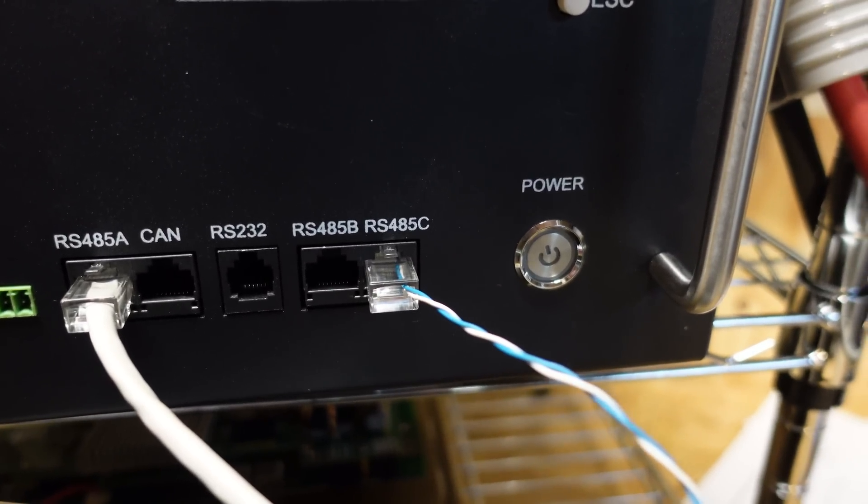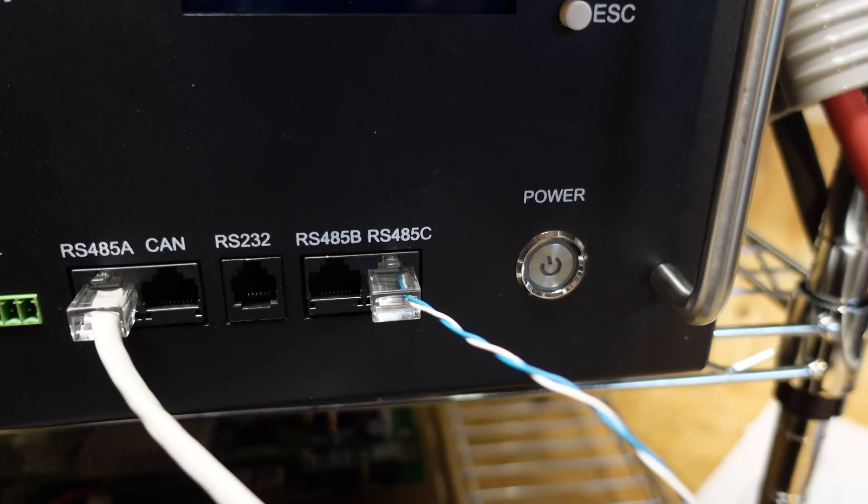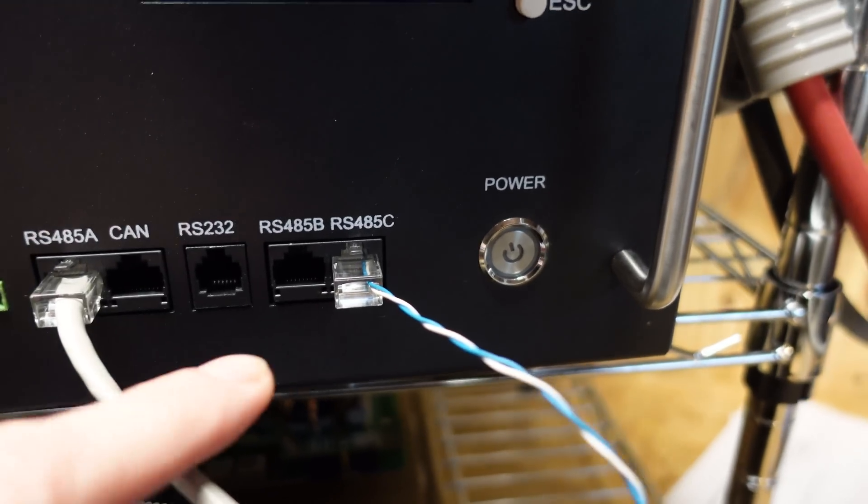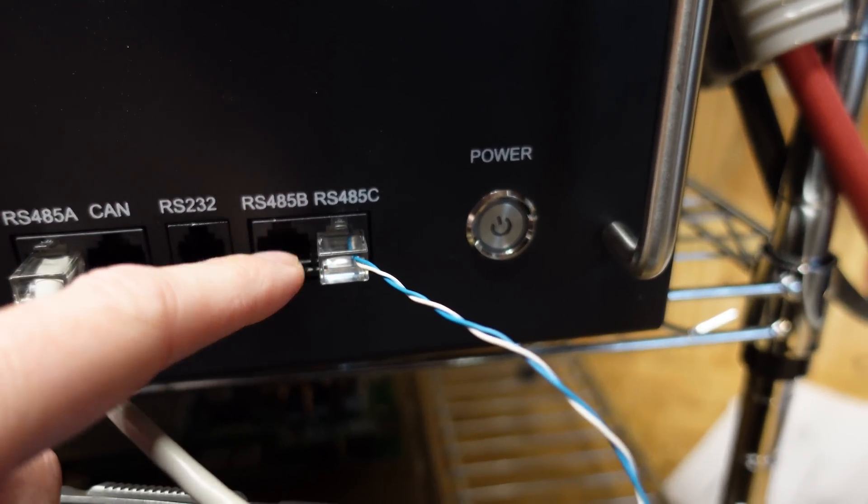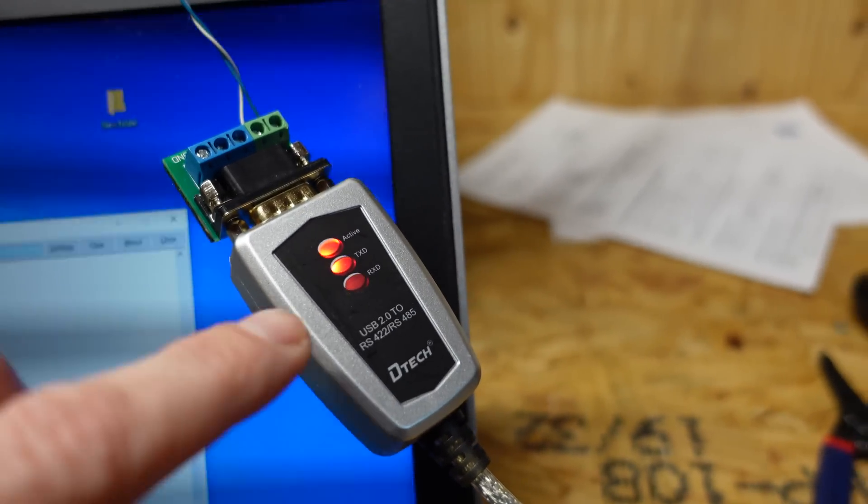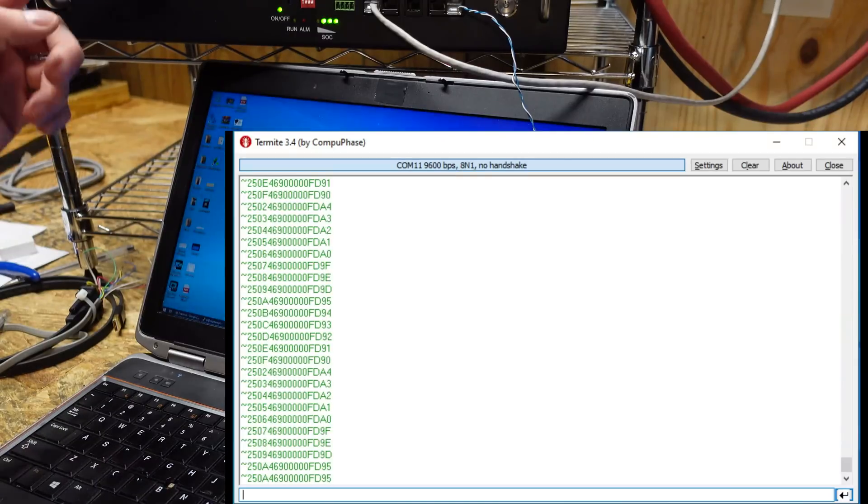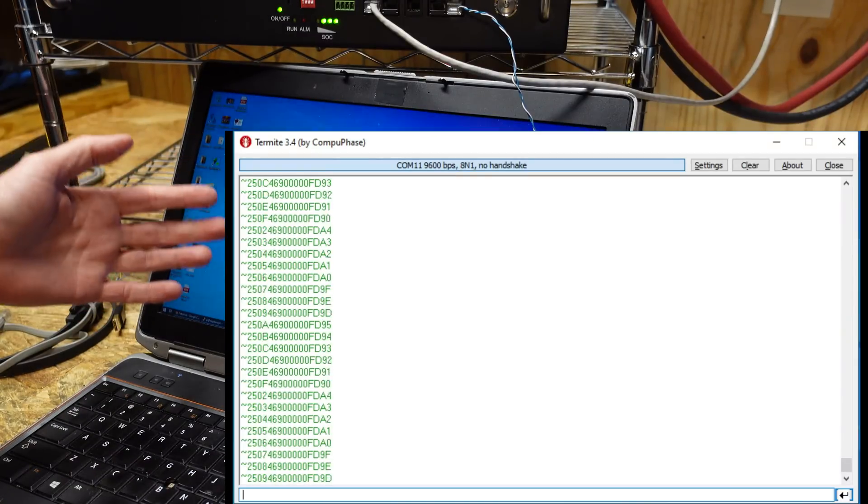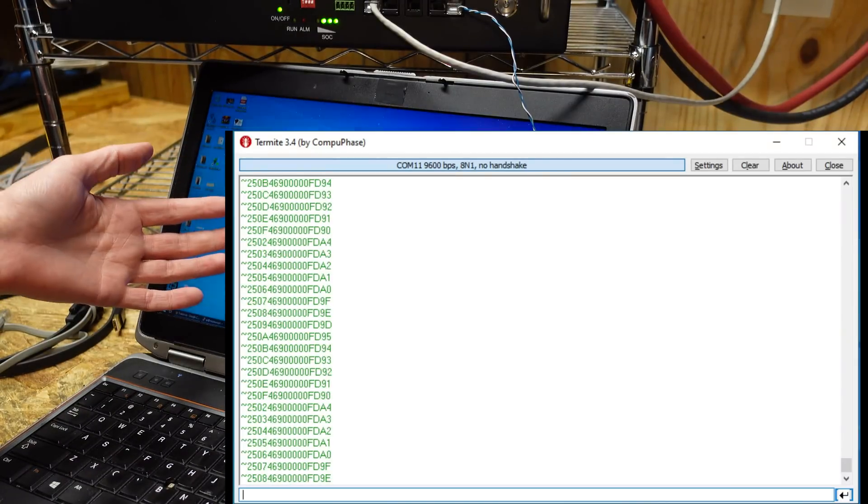All right. So, I've got it plugged into RS-485C just to demonstrate that the pinout of this cable, just to demonstrate that the pinout of the pins are correct. So, that's going down to this adapter. You can see the receive lights blinking. And on the screen here, we can see that it is clearly receiving data. So, we know the pinout there is correct.